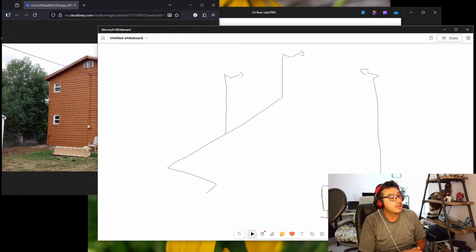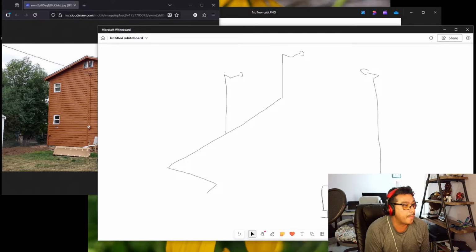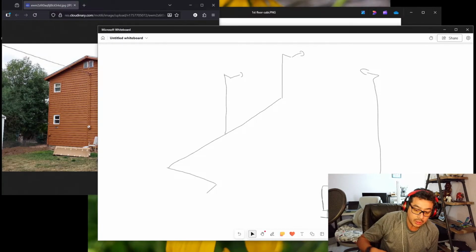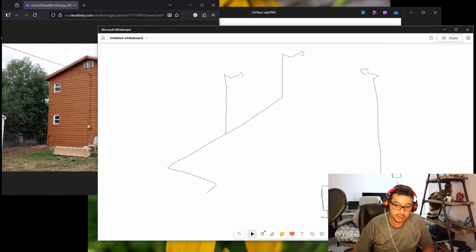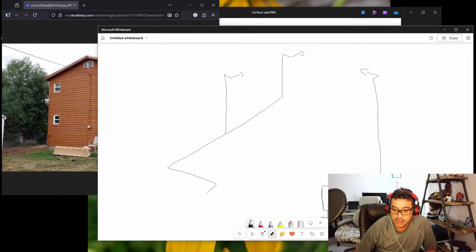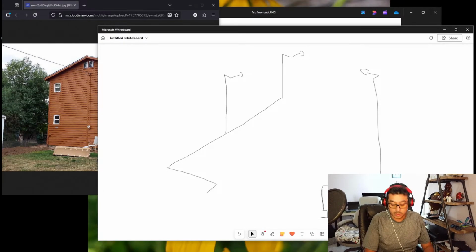Why? Because more than likely, we always have to be aware that it snows. And if snow is there, you have to raise your condenser as high as we can. So we got 18 inches there, and then we know that we have another 6 inches to our connections.